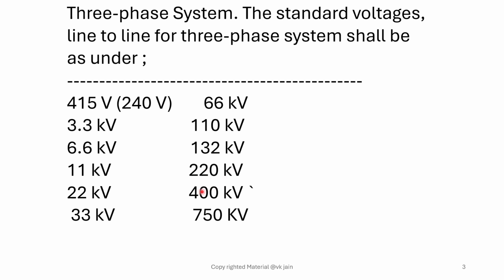These voltages from 110 to 400 kV and 750 kV are the transmission voltages in India, whereas 66, 33, 22 and 11 kV are the so-called high voltage systems, standard voltages in India. Then we have the three-phase voltage as 400 standard. It should be this.